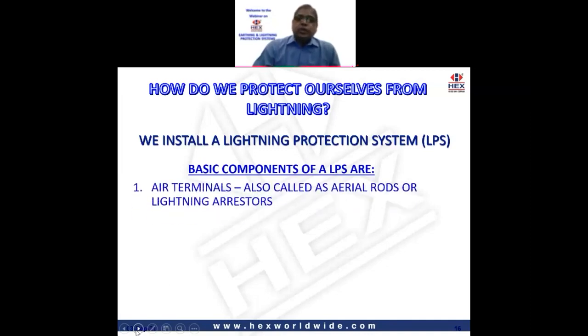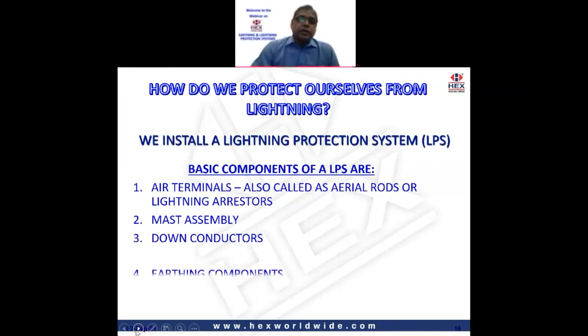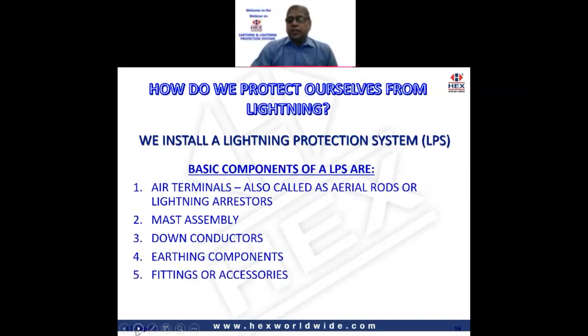Air terminals, also called aerial rods or lightning arresters. Mast assembly on which the lightning arrester is installed. Down conductors, which provide a safe path for the lightning to be grounded. Earthing components, which will disperse the lightning strike into the earth. And fittings or accessories that are used to connect all these components. This is the simple way of describing a lightning protection system.